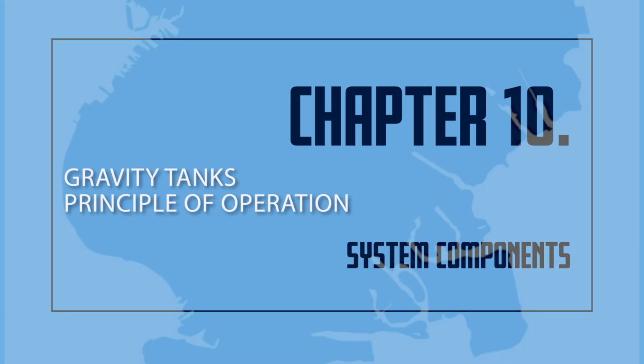A water tank can be used if the tank supplies the pump due to gravity. In other words, the weight of the water forces the water to flow into the pump. This type of water tank is called a suction tank. The water flows from the tank through the supply inlet into the pump. As the water passes to the center of the pump, it reaches a rotating impeller. This impeller is designed to grab the water on the inlet side of the pump and then discharge the water under increased pressure into the fire protection system.